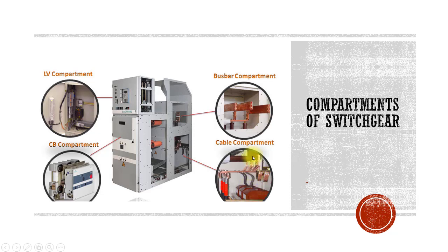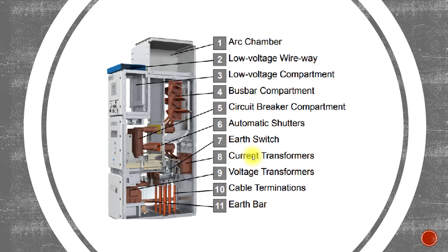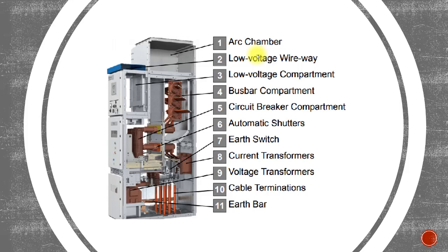You can also see the connection for the voltage transformer installed in the cable compartment. Now looking at another type of switchgear design: number one is the arc chamber. Most companies are now going for the arc chamber. The reason is that if there is any arc in any compartment, flappers are provided, and if there is an arc in the busbar compartment or circuit breaker compartment, these flappers will open with the pressure and direct the arc through this arc chamber, which is normally required to vent outside of the building.